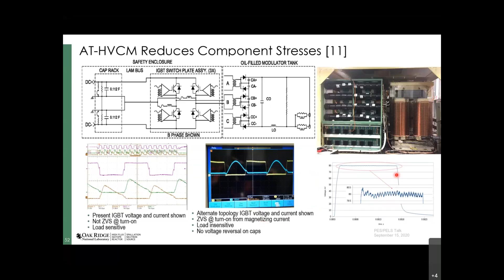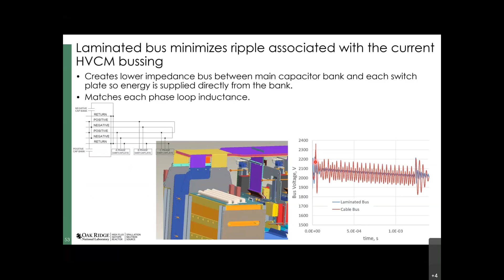Another thing we employed is what's called a laminated bus. We did away with the cable bus I showed previously, and we were able to go from a situation where the ringing on the cable bus was quite high, shown in red, to using the laminated bus where the ringing was reduced by at least an order of magnitude, which was quite effective. This was developed by a company in Rochester, New York called Mersen, and it's one of the biggest laminated bus bars they've ever built, about 8 feet in length and weighing several hundred pounds, so quite impressive.